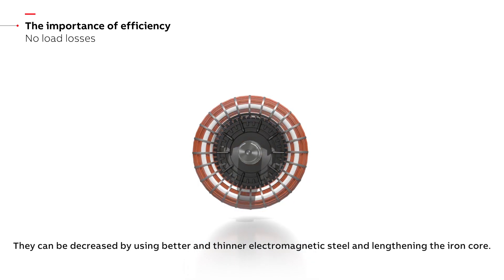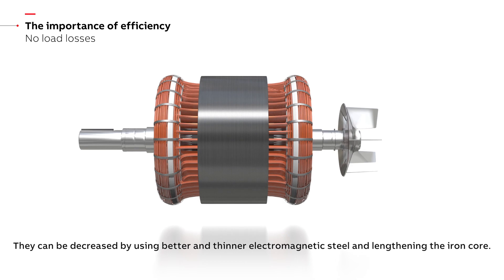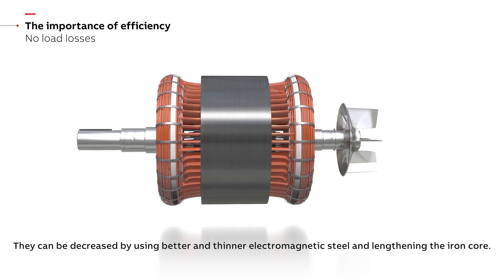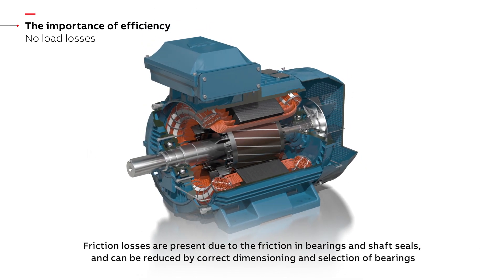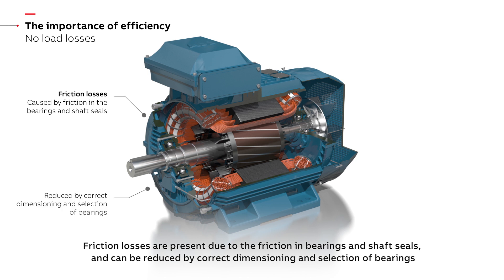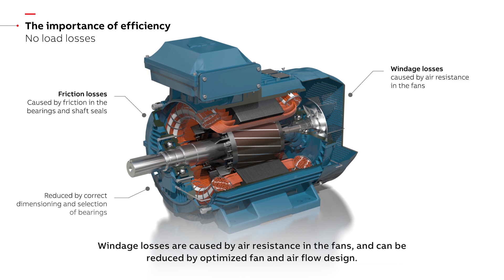Stator iron losses can be decreased by using better and thinner electromagnetic steel and lengthening the iron core. Friction losses are present due to friction in bearings and shaft seals, and can be reduced by correct dimensioning and selection of bearings. Windage losses are caused by air resistance in the fans and can be reduced by optimized fan and air flow design.